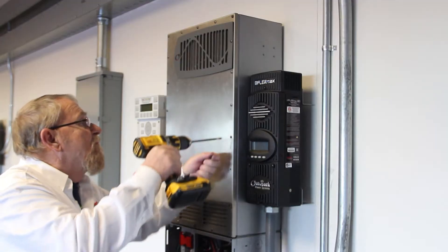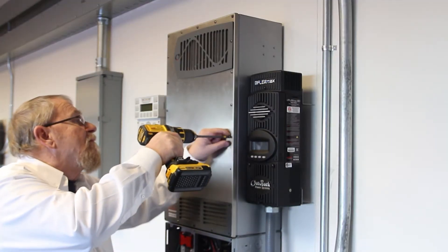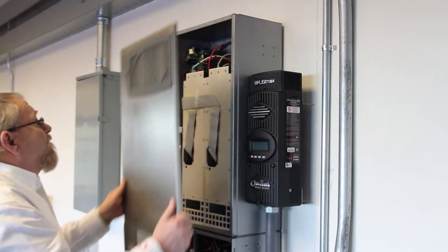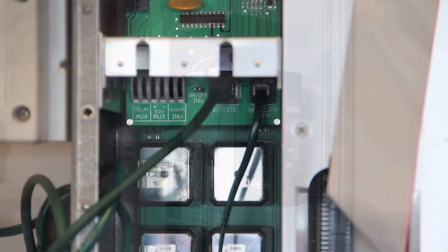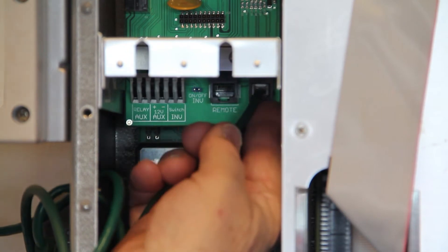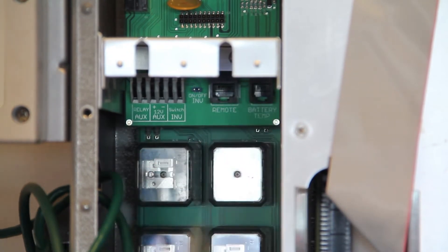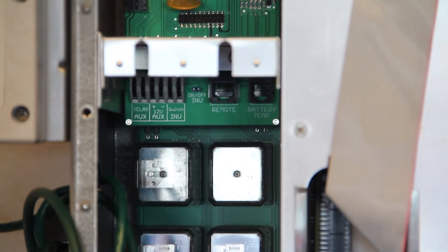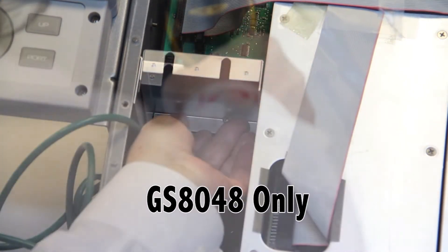Next remove the 22 screws that attach the cover to the chassis. Disconnect the RTS or remote temperature sensor and communications cable from the control stack. For model GS 8048 only, remove the control stack center plate by unscrewing the two Phillips screws.